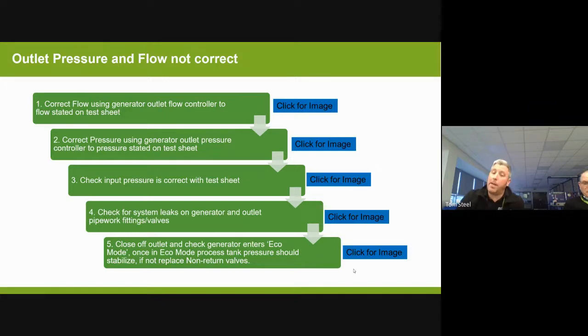And then we're going to check it goes into an eco mode. Now, eco mode itself means that if we have no demand from the generator, then the tank pressure, that's the process tank that's associated with the oxygen generator, should increase slightly. And as that increases slightly towards the input pressure, we've got a pressure switch that monitors that, and it basically closes the system down. That's to save any unwanted air usage. For example, if they're not using it for something like 3-4 hours, then it should go into this eco mode, and it should save air created by the compressor, because we all know air created by a compressor costs money. And then we just open up, and it should go into its normal operation on its own.